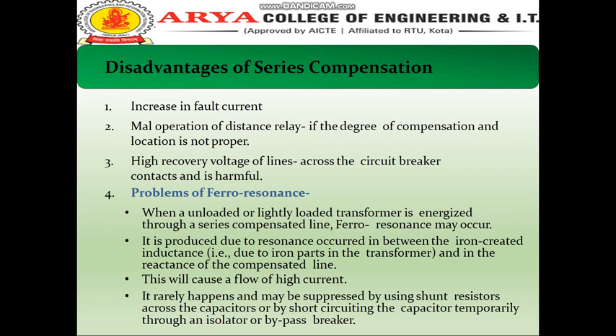When an unloaded or lightly loaded transformer is energized through a series compensated line, ferroresonance may occur. It is produced due to resonance between the iron cored inductance and the reactance of the compensated line. This will cause a flow of high current. It rarely happens and it may be suppressed by using a shunt resistor across the capacitor or by short circuiting the capacitor temporarily through an isolator or bypass breaker.